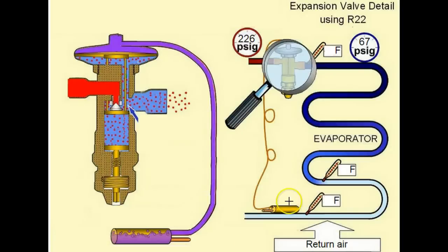So now the system is running and we're at 60 degrees Fahrenheit here. 60 degrees Fahrenheit is 102 PSIG in this bulb. And in this suction line at 60 degrees, that suction pressure is 102 PSIG as well. So our opening and closing forces, no matter what happens, balance. They are balanced out with equal force.